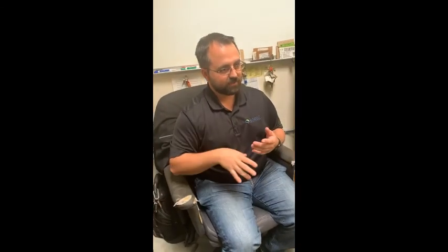And this also is not necessary for the system to run. None of the logic is being done here, besides some things like when you reset an alarm. So if the Foundation wants to get into it on their side, from whatever computer they're using over there, this has to be on. If this shuts off and they still have power there, they're not going to be able to see their buildings.